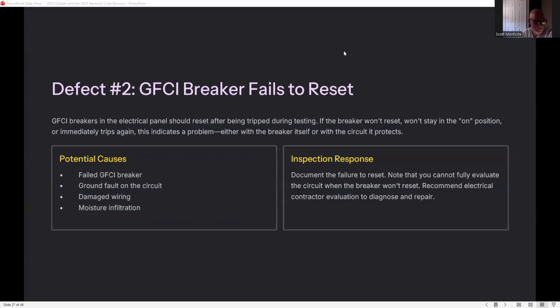Defect number 2, GFCI breaker fails to reset. The GFCI breakers in the electrical panel should reset after being tripped during testing. If the breaker won't reset and won't stay in the on position or immediately trips again, this indicates a problem, either with the breaker itself or with the circuit it protects. Potential causes: a failed breaker, a ground fault on the circuit, damaged wiring, moisture infiltration. Inspector response: document the failure to reset. Note that you cannot fully evaluate the circuit when breakers won't reset. Recommend an electrical contractor evaluate, diagnose, and repair.